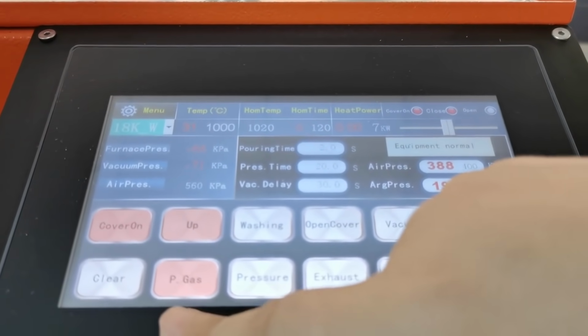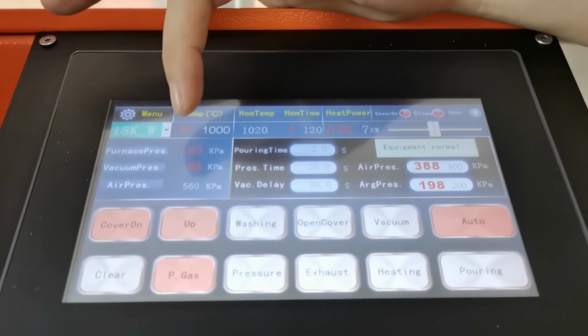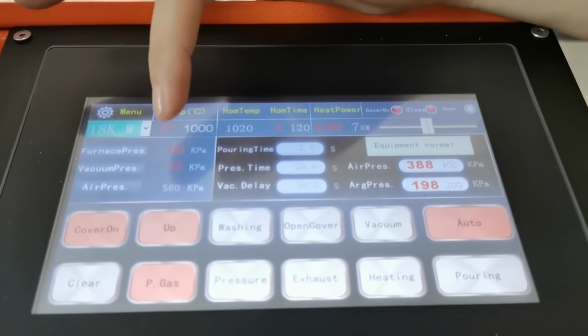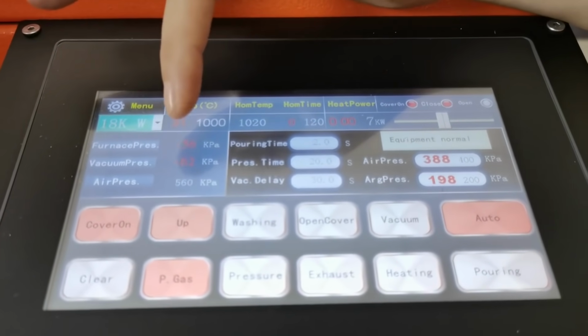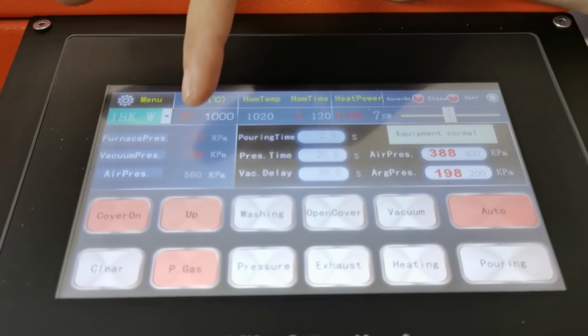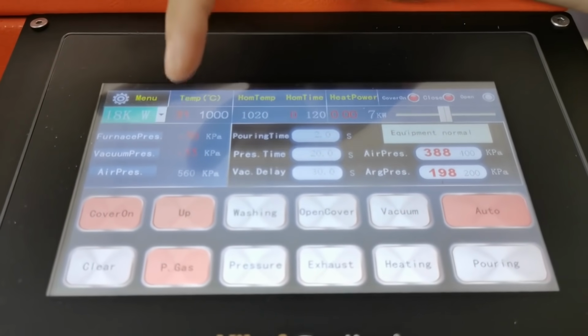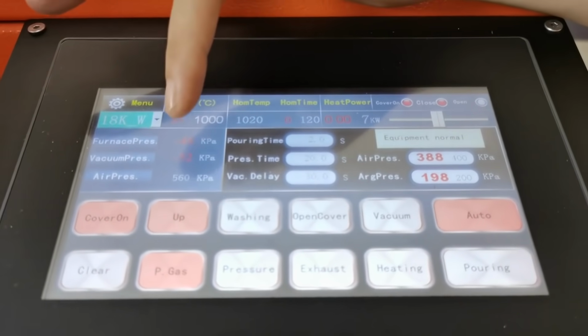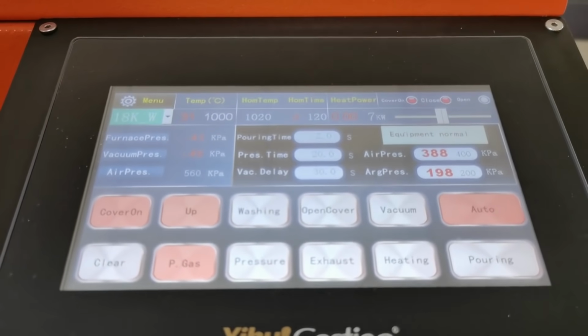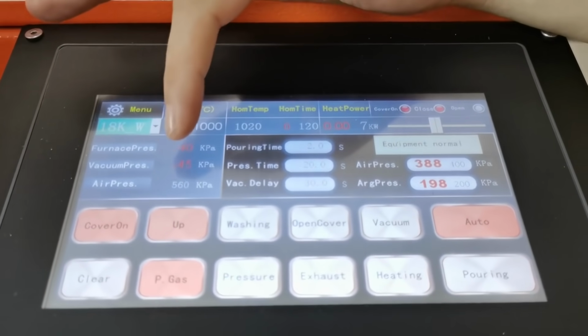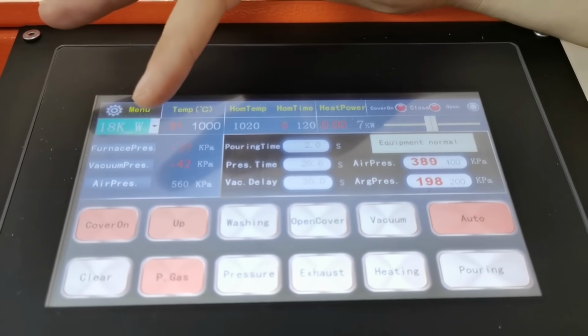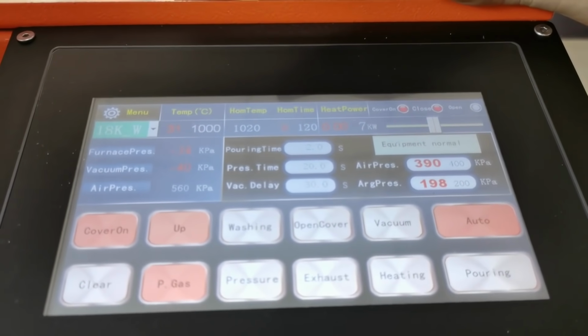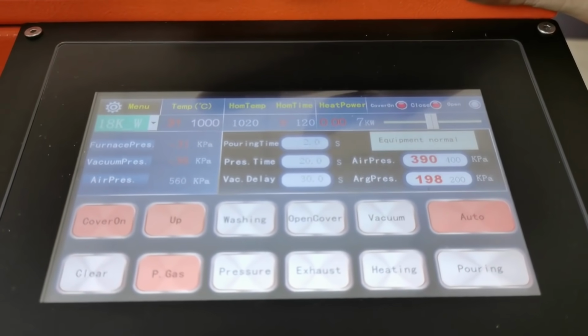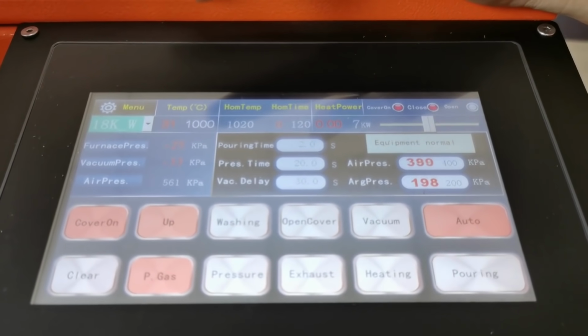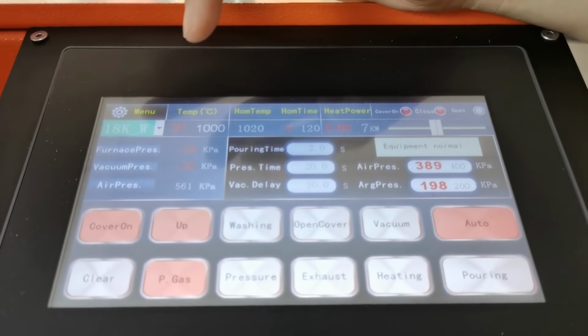pouring argon gas. After the argon gas pouring starts, you can see here, the pressure is changing. Once we see here the pressure becomes a positive value, the argon gas will stop. It may take about 30 minutes to have the pressure become a positive value. So this, it is still minus value, means the argon gas is still working. It's -38, 30, 27. We still have to wait.